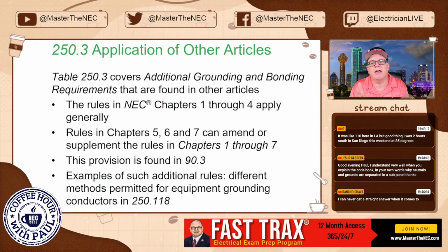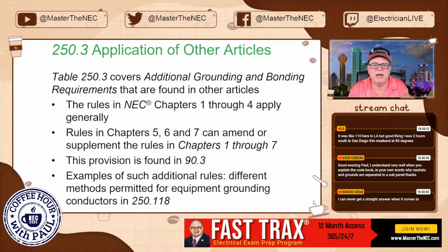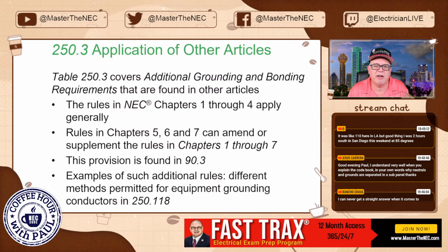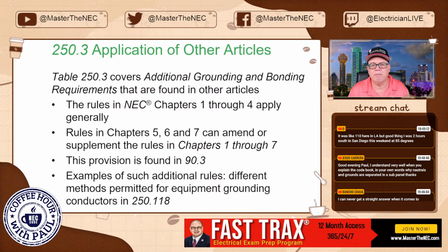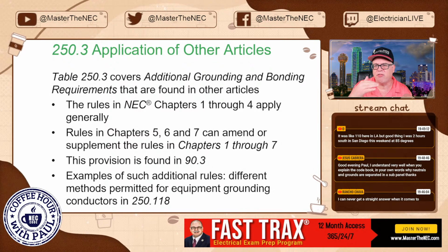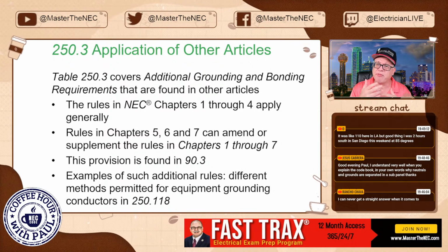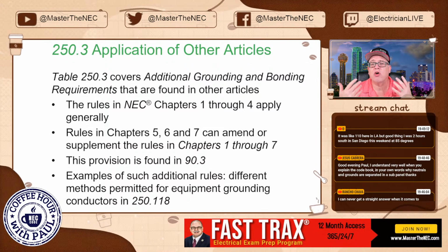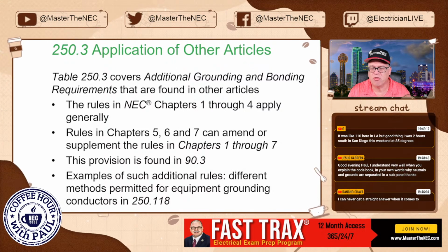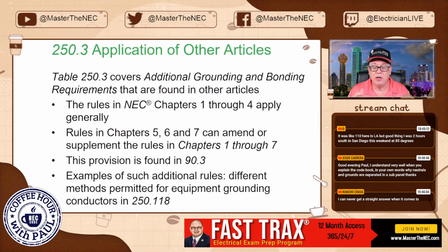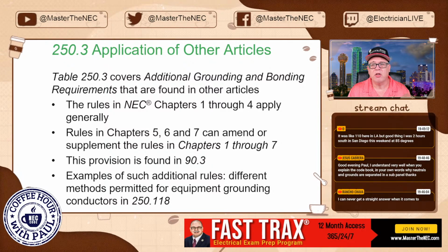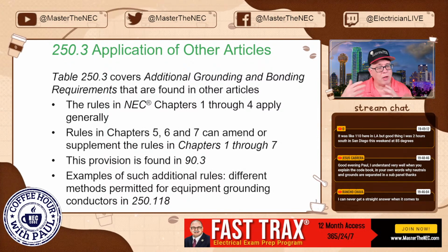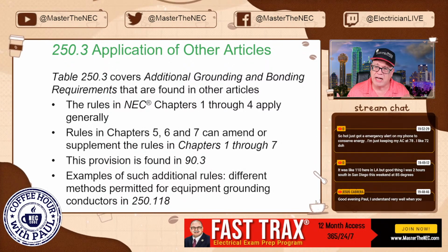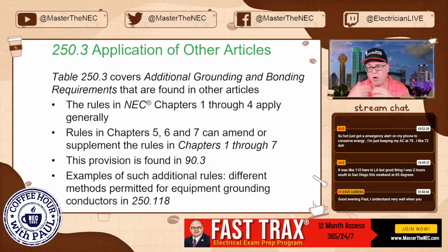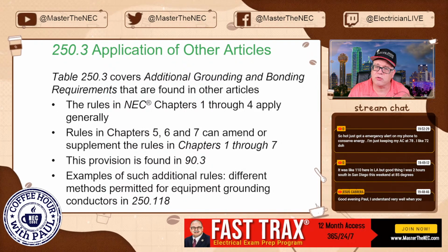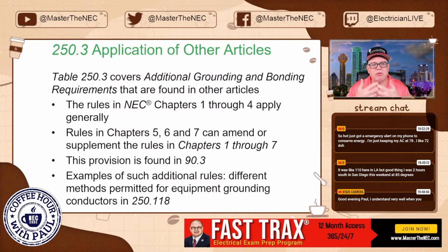Okay. Examples of such additional rules: different methods permitted for equipment grounding conductors in 250.118. 250.118 gives you the list of different types of things that qualify as equipment grounding conductors. Okay. So you'll get this list, and that's in chapter 3. So a good example here is you've got the different wiring methods. Some of them qualify as equipment grounding conductors, and whatnot in chapter 3. And they'll have their own rules, but then you've got the rules in Article 250. So they intermix between each other.